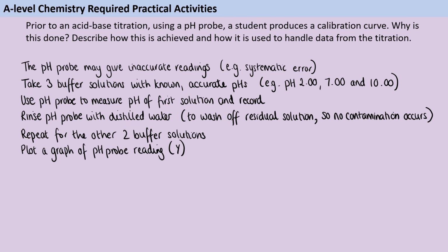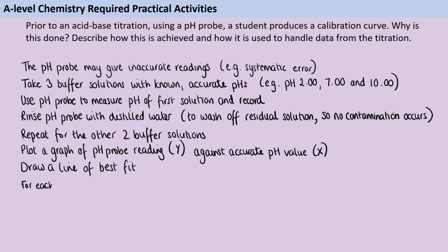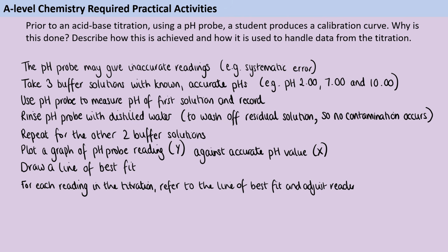So having done those, you can make your calibration curve. So this is where you're going to plot the graph where you've got the pH probe reading on your y-axis and the original accurate pH value on your x-axis. And it's very likely that this will be a linear graph, even though we call it a calibration curve. That's just the name of the graph. So once we've got that, we can draw a line of best fit through our data. And then for every reading that we make in the titration, you're going to refer to that line of best fit. So you might read off that your pH probe is saying this is a pH of 9.10, but actually when you track across to your line of best fit, you say, actually, that's a pH of 9.00. And so you add an extra column to your table and you adjust your results accordingly.